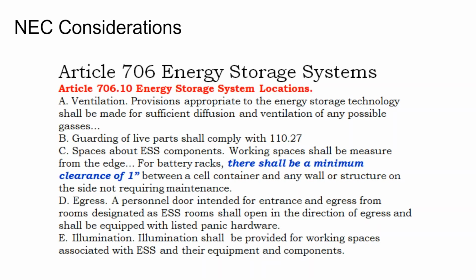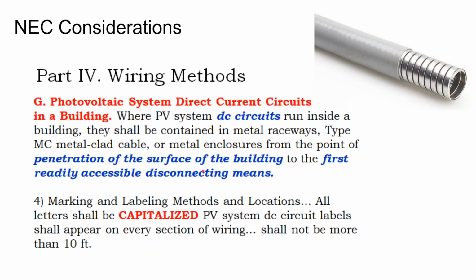ventilation requirements. One thing that jumped out at me is, even if you don't have to access the batteries for maintenance purposes, you should put a 1-inch clearance between any wall and your battery bank. So a little bit more requirements for higher voltage batteries than there are for low voltage batteries.